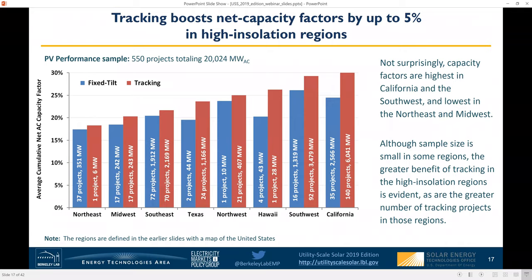For those who prefer to think geographically rather than in terms of insolation, this graph breaks out the same capacity factor data on a regional basis. The overall rankings shouldn't be too surprising — the Northeast and Midwest have the lowest capacity factors, while the Southwest and California have the highest. Tracking provides more of an incremental benefit over fixed tilt in the high capacity factor regions than in the lower capacity factor regions, and as a result we see a lot more tracking than fixed tilt projects in those high capacity factor regions.